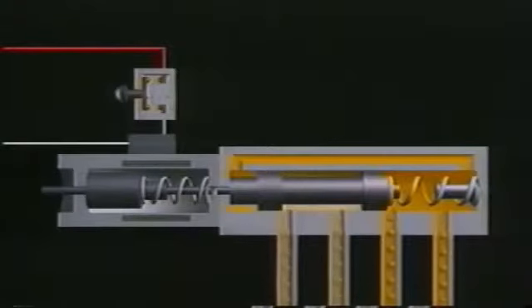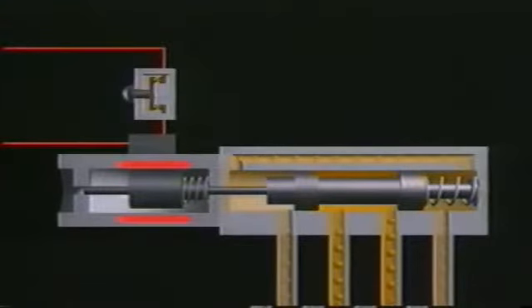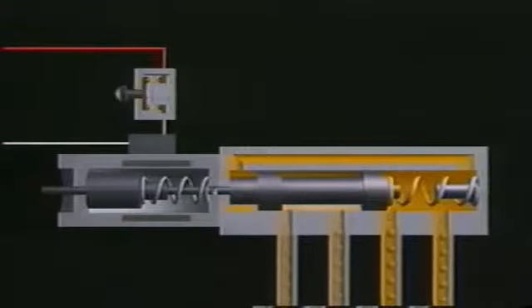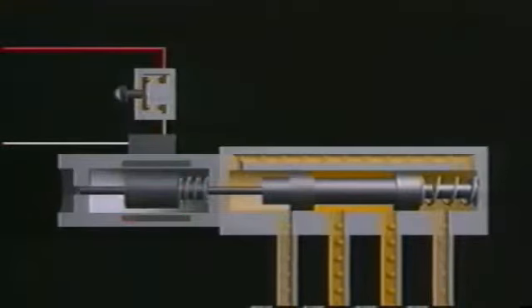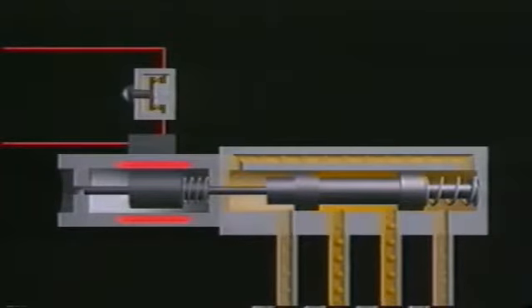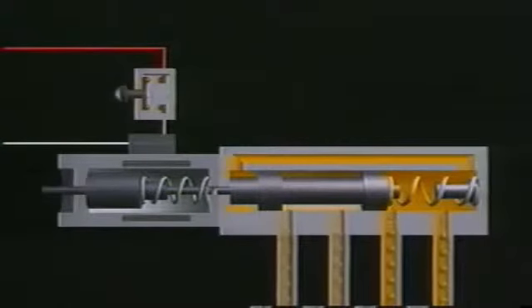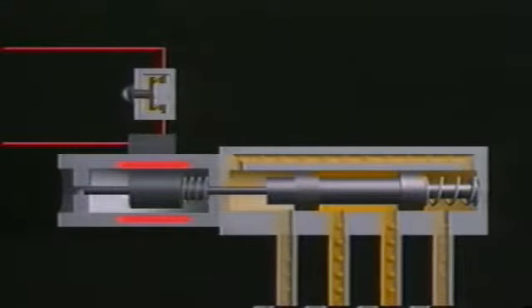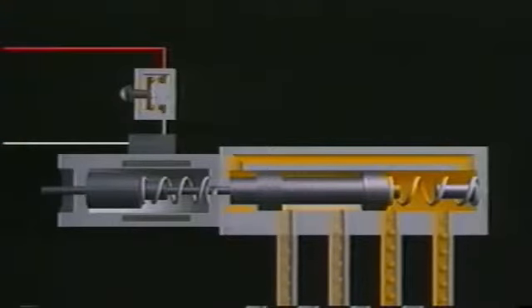This hydraulic 4/2-way valve clearly demonstrates the function of a solenoid valve. Switching from the initial position takes place as follows. On one side of the valve is a solenoid. Its core acts as an armature, exerting a force on the control piston of the valve. If the coil is energized, an electromagnetic field is produced. The armature is pulled against a spring to the middle of the coil. As a result, it pushes the control piston of the valve into the other switch position. The valve remains in this position as long as the electrical signal is present. When the current is interrupted, the magnetic field, and therefore the magnetic force, collapse. The return spring pushes the control piston and the armature back into the initial position.